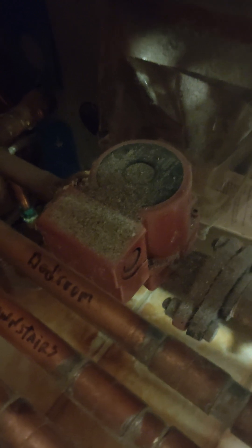This pump is 20 years old and I've never had to replace it, luckily, for two reasons. Number one, they didn't put shutoff valves on either side — big mistake by the installer — but that's okay. Luckily it's at the bottom of the system, so no air gets stuck in it. It just runs and runs and runs. I bet I never have to replace it.